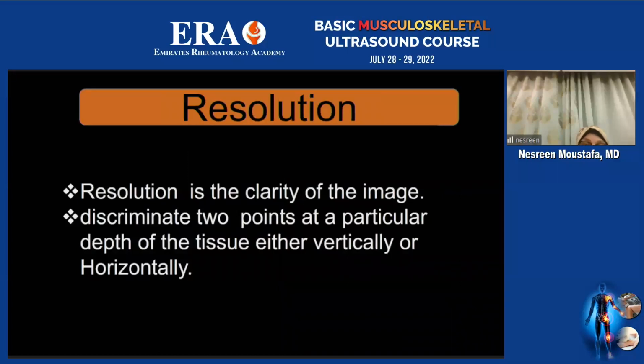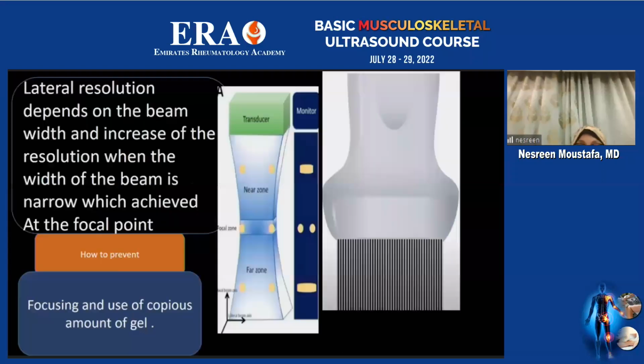Resolution, Dr. Ahmed is talking about it now. Resolution is very important, and it's the clarity of the image, the ability to discriminate two points at a particular depth of the tissue, either vertically or horizontally. And we know that the linear probe is the best one for more clarity because of the contact between the lines of the sound waves, and it depends on the beam width. It increases the resolution when the width of the beam narrows at the focal zone.